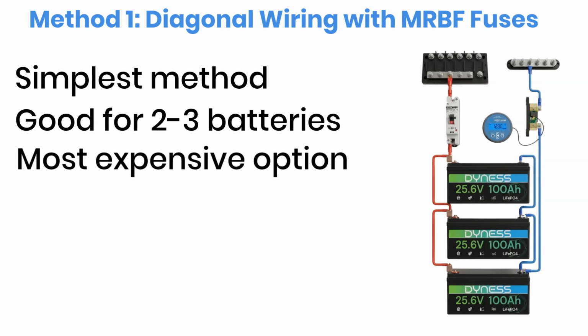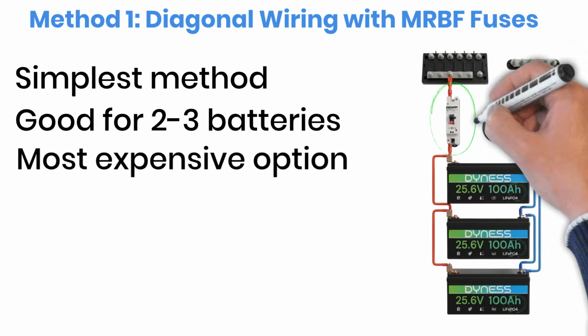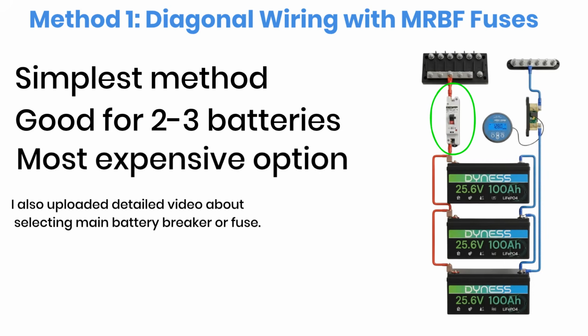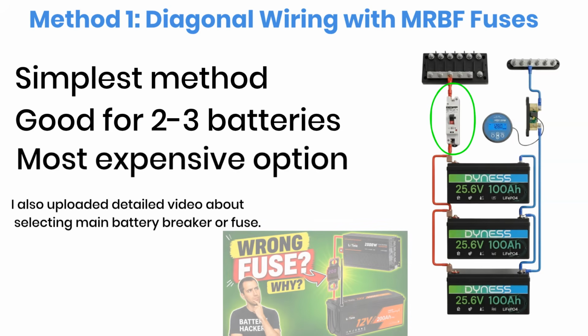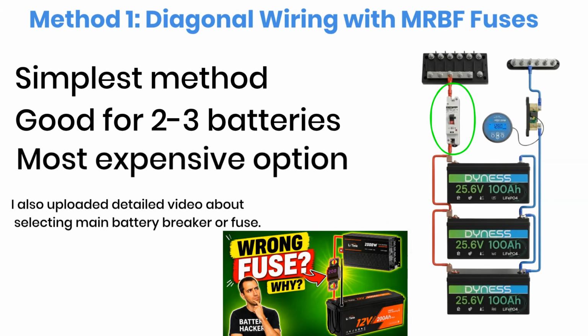If you want an easy way to disconnect the entire battery bank for maintenance, you can also install a main direct current breaker between the batteries and the system bus bar. That gives you a single switch to isolate the battery bank whenever you need to work on the system. Just remember that this main breaker or fuse must be rated to safely interrupt the maximum fault current that the complete battery bank could produce, not just the current from a single battery.